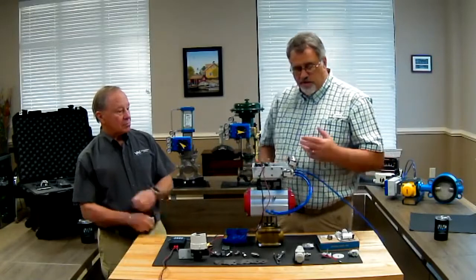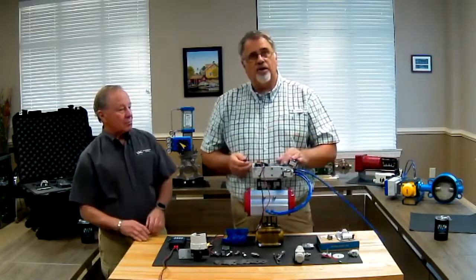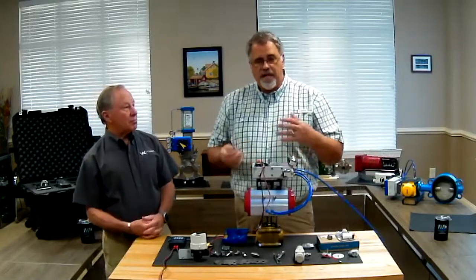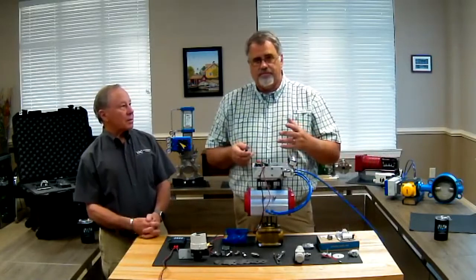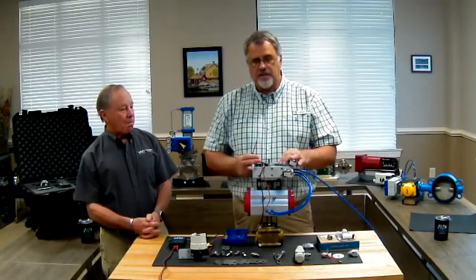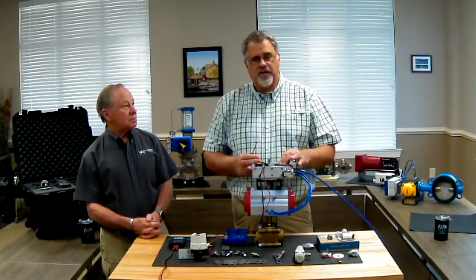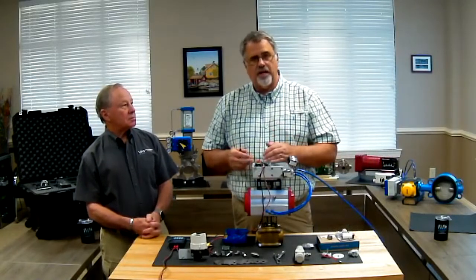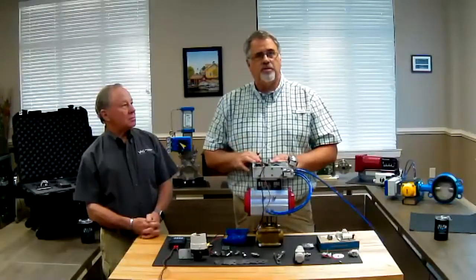There we go, that's how quickly you can calibrate the positioner. Compared to many other products, this calibration process is many times faster because we directly set 0 and span at 4 and 20 milliamps.